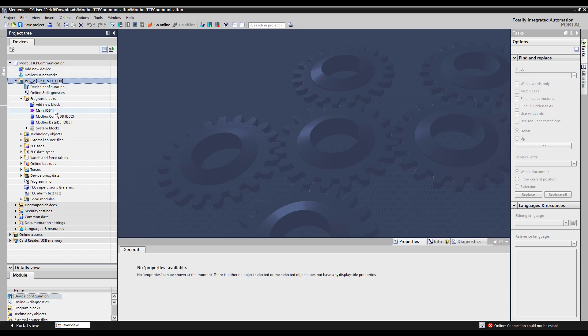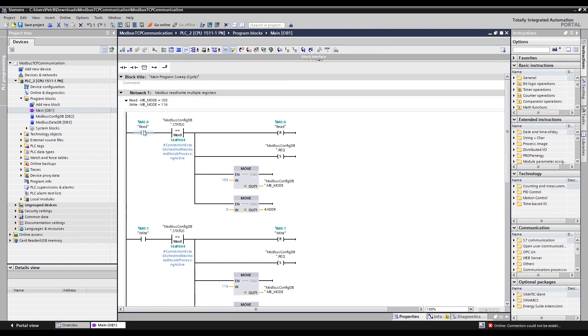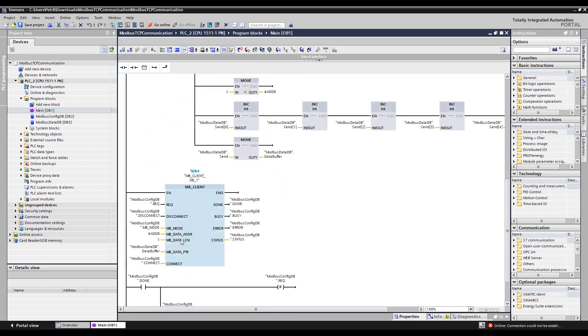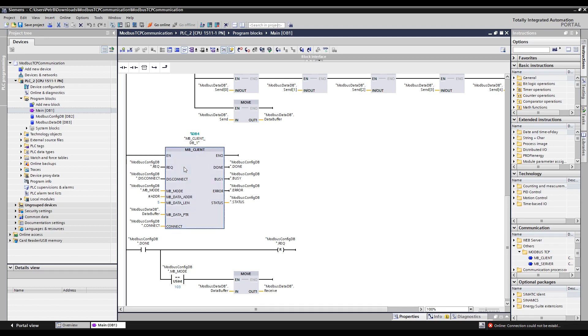I'll open up the main OB1 — this is where all the magic happens. There's logic for reading, for writing, and the main block for Modbus communication is MB_Client. You can find it in the Communication tab under Others > Modbus TCP. Client means the PLC is controlling the communication; the other device is just waiting for a connection.